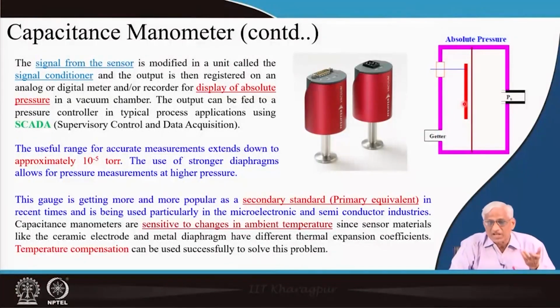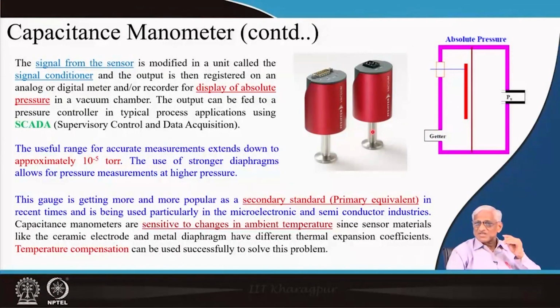SCADA can be used to process the analog signal from this capacitance gauge, giving it to controllers so the process can be controlled in chemical or pharmaceutical processes etc. These are very important. I do not use the gauge only for measurement; I also use it to control some other process, like to open a valve in a process industry.